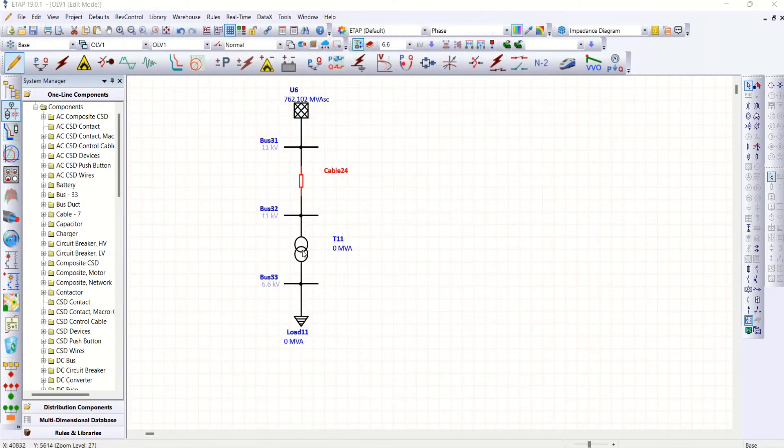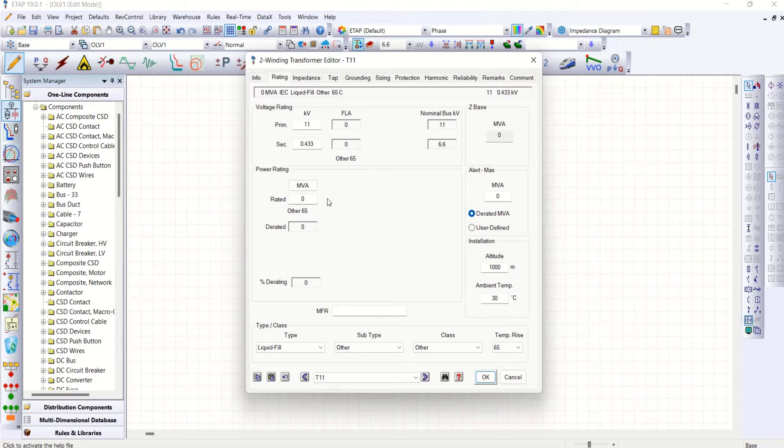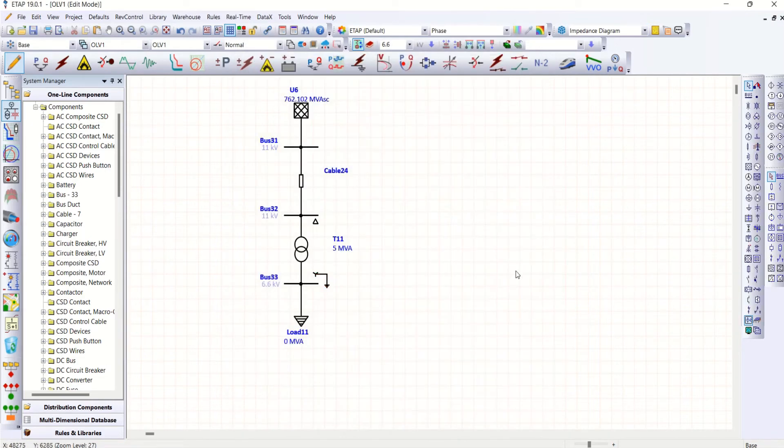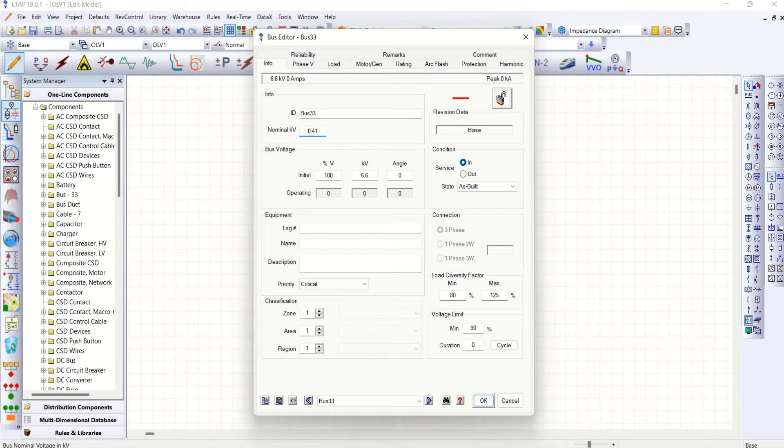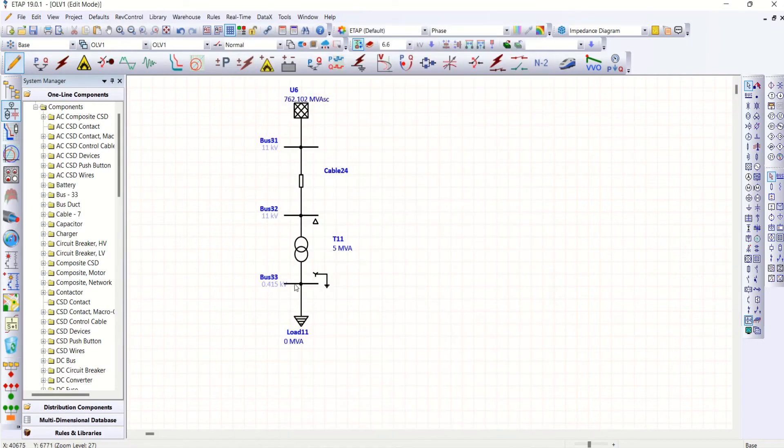So this is 11 bar. I'll go for 0.433, 5 MVA transformer. Impedance take typical value. Grounding delta star as usual. Then this is 0.415. That's it. This is 5 MVA transformer.